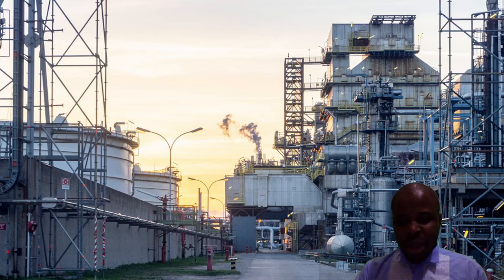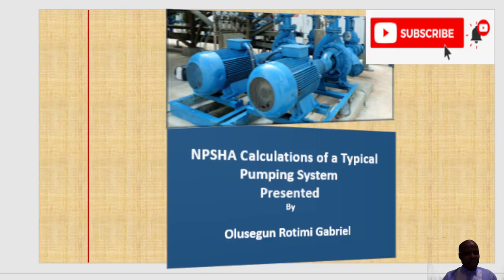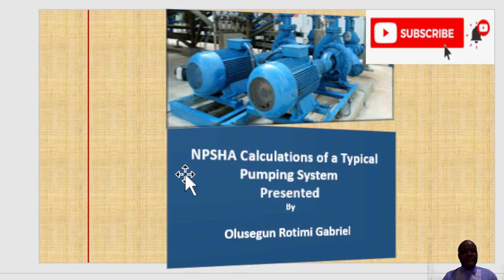Today we are going to be looking at a very important topic as far as pumping systems are concerned — we are going to be looking at NPSHA calculations of a typical pumping system. On this channel we have looked at NPSHA, which is the net positive suction head available, and NPSHR, the net positive suction head required. NPSHA is your system characteristic and NPSHR is the pump characteristic.